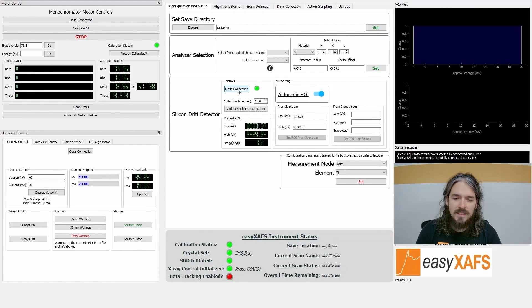Next we can initialize the connection to the detector. Since I already have the shutter open and the beam is on the detector, I can hit Collect MCA Spectrum, and the detector acquires a 1-second spectrum. You can see this spectrum at the top right. Since we're using an SDD detector, we're measuring the number of X-rays and the energy of each X-ray acquired, so we have an energy spectrum of all of the X-rays measured. The energy scale goes from 0 to 40 keV. For the silicon 551 analyzer, there's a single intense peak from the monochromatic beam, at around 8.5 keV. These are the X-rays that we're interested in.